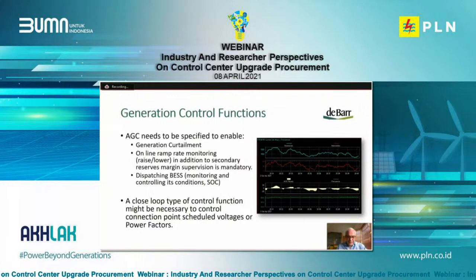In addition, there are some additional functions that have been added to control centers, some of which are added to the generation control, intended to do closed-loop control of voltage at scheduled interconnection points, or power factor control at specific locations in the grid.